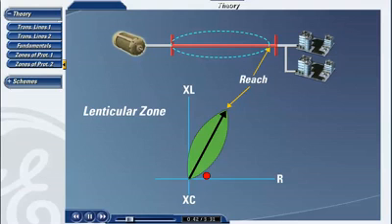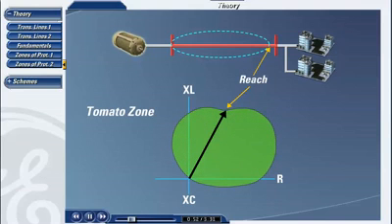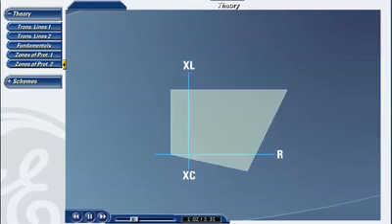As a side note, the D60 relay also gives the protection engineer the ability to configure the MHO characteristic into what is known as a tomato-shaped zone. A tomato-shaped MHO characteristic allows for faults that have more of a resistive element to fall into its zone of protection.